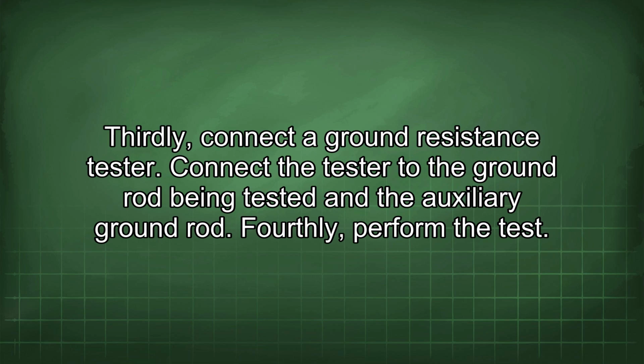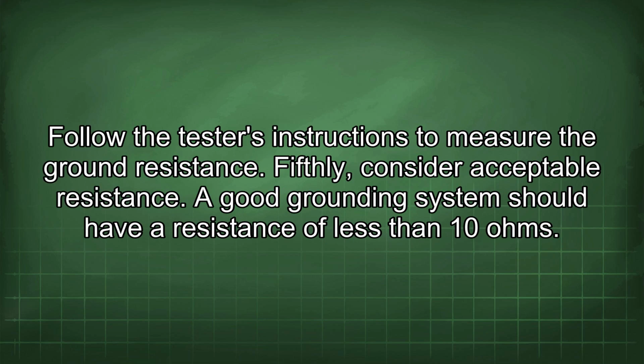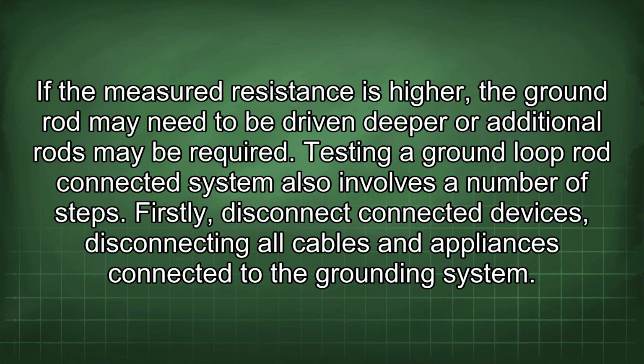Thirdly, connect a ground resistance tester. Connect the tester to the ground rod being tested and the auxiliary ground rod. Fourthly, perform the test. Follow the tester's instructions to measure the ground resistance. Fifthly, consider acceptable resistance. A good grounding system should have a resistance of less than 10 ohms.